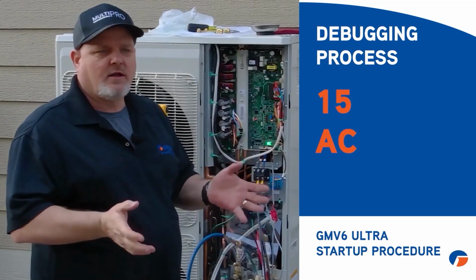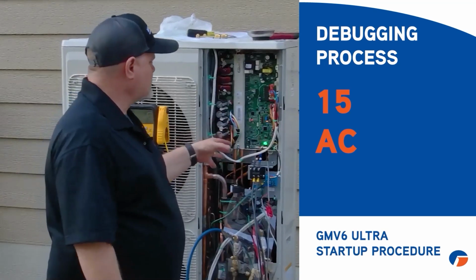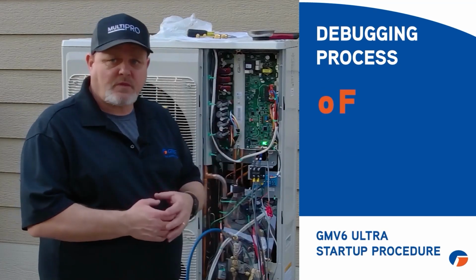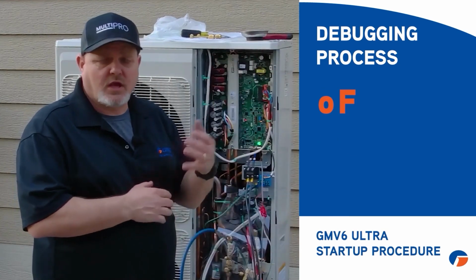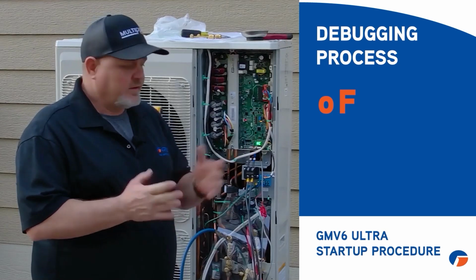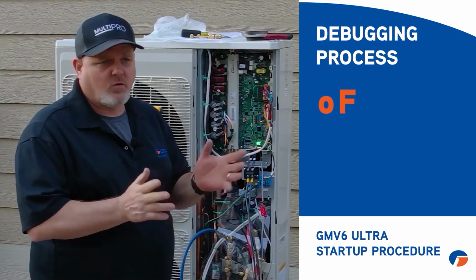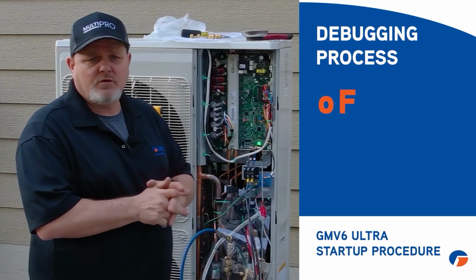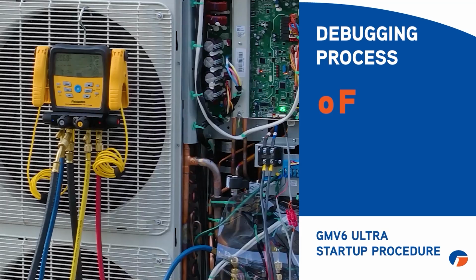When it's done, you'll come back to the machine. It'll say OF, meaning off, and all of your indoor units will say off as well. And then you're good to go. Then you can just set it to heat or cool, whichever season you need to put it into, and let it run. While it's running a debug, especially if it's running debug in cooling, you can add your additional charge at that time. A couple other things I want to point out.